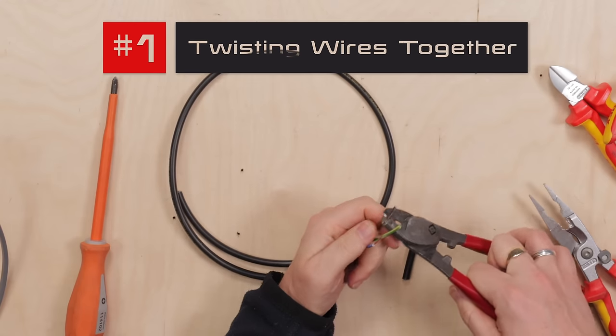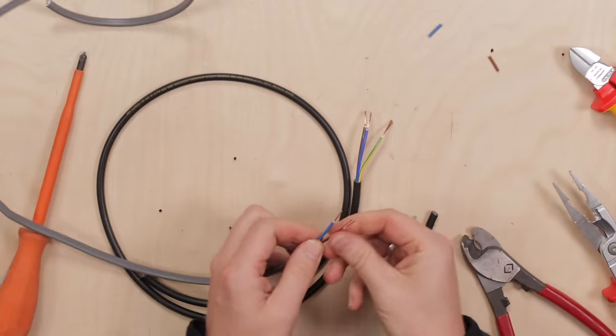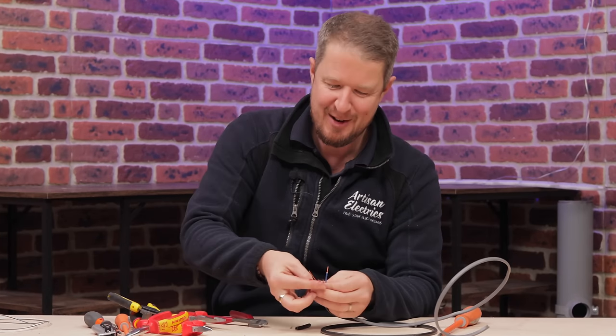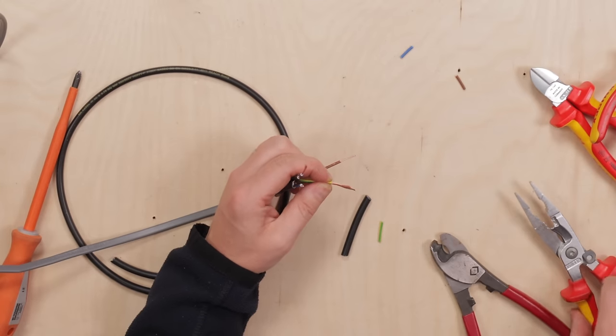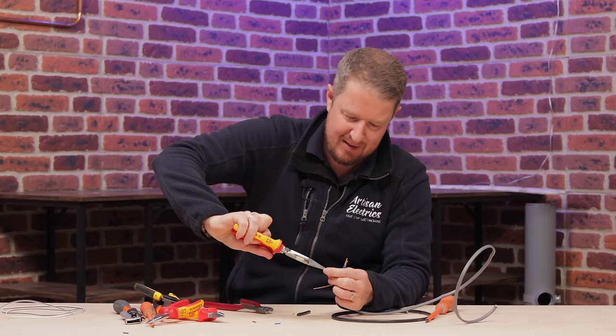The first DIY mistake that we see quite often as electricians is when people do this. They strip the wire back, take the ends off to expose the copper, all good so far, and they want to join two wires together. So what do they do? They get the wires and they do the old twisty twisty. Twisting the wires together. I've seen it with stranded conductors, I've seen it with copper solid conductors.